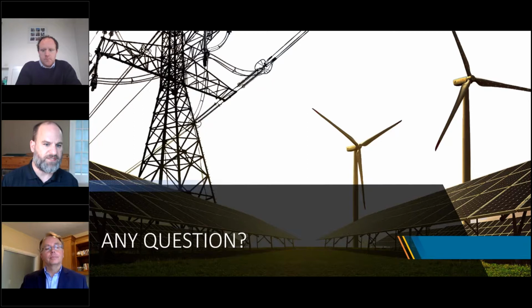Which looks like this: you start with your starting load flow, so you've got one generator topology, and then you want to inject a new generator topology, but make sure you're locking out all your taps, and locking out all your cap banks so that your primary voltage control is fixed, then you start tweaking and sending signals into your load flow.